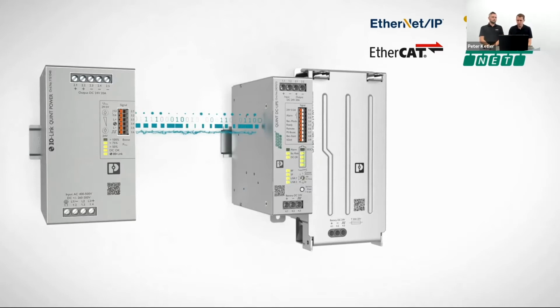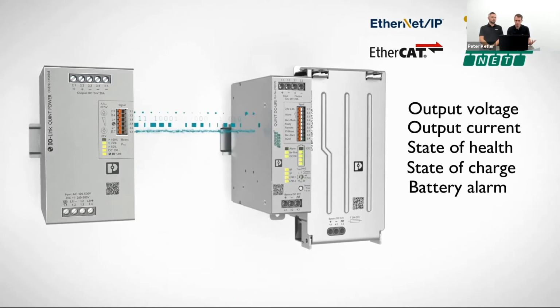Let's have a look at the features you find on the UPS system, which will also be provided: output voltage, output current, and state of health, which is the battery lifetime - very important, it enables you to have good information about the upcoming remaining lifetime, and also enables preventive maintenance. The state of charge is also very important to know whether your current battery in the charging state can buffer your application. And battery alarm is also important in order to have a push message to the PLC about whether the battery has damage and cannot work.